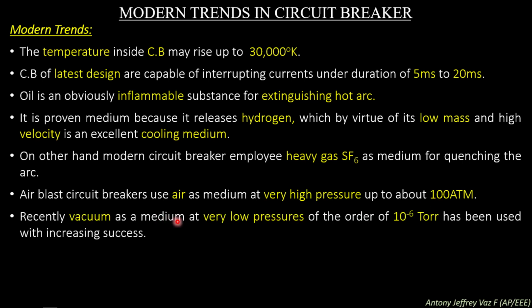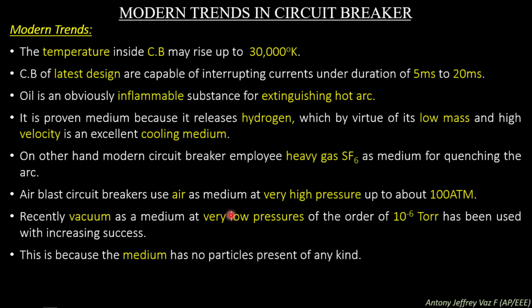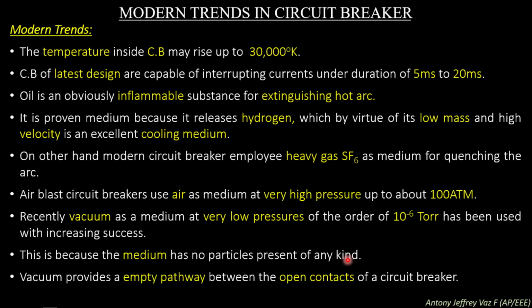Recently vacuum as a medium at very low pressure, of the order of 10 to the power minus 6 torr, has been used with increasing success. So similar to the pressurized air blast circuit breaker, vacuum is also used as a medium to interrupt the arc. Very low pressures of the order of 10 to the power minus 6 torr are increasingly used in successful circuit breakers nowadays. This is because the medium has no particles present of any kind. So in a vacuum circuit breaker, the medium is a vacuum. Vacuum provides an empty pathway between the open contacts of a circuit breaker. So in a vacuum circuit breaker, the contacts are separated inside a vacuum.